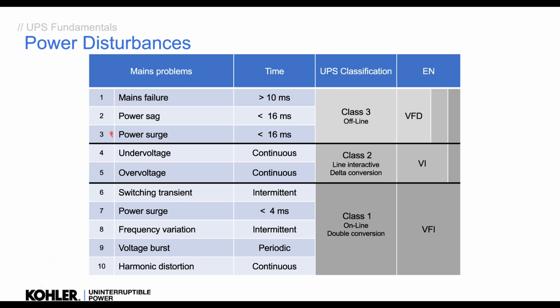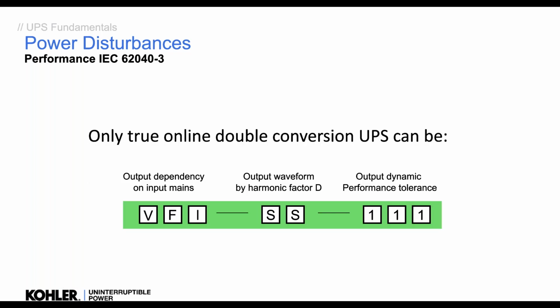So we have, just for mains failures, sags and surges, if you can have a little break, an offline VFD UPS. If you want to protect against under and over voltages, we have a VI UPS, voltage independent. But to protect against everything, switching transients, power surges, frequency variation, harmonics, we need an online double conversion VFI UPS. Okay, and this is classified, as I said, 62040.